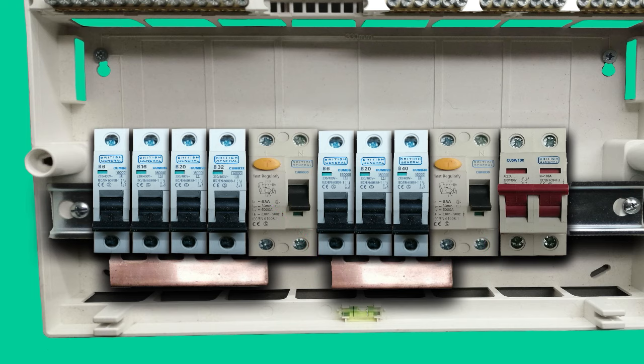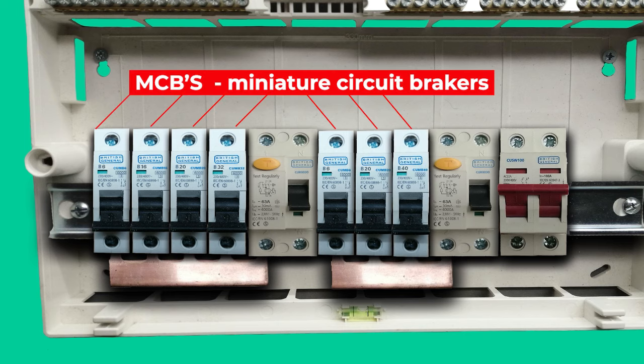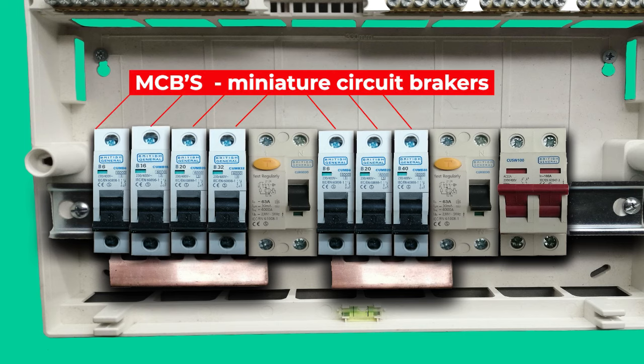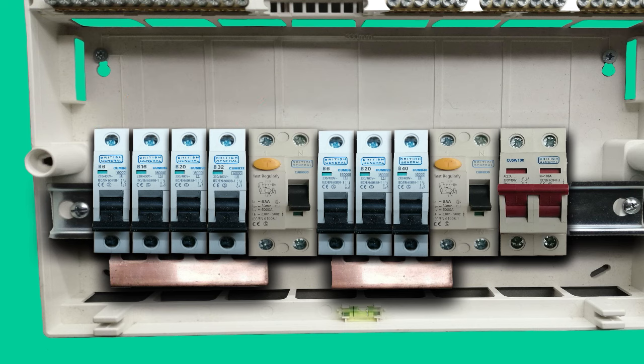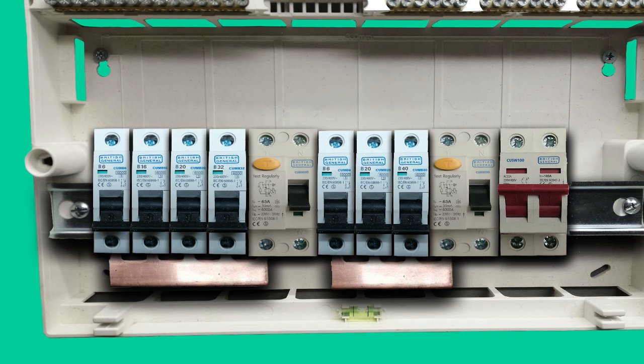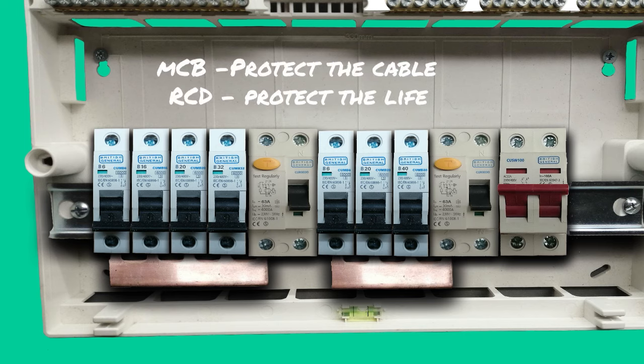And next to the RCDs we've got MCBs or mini circuit breakers. Each one of the MCBs protects one of the electrical circuits from overload as well as short circuit, which can cause damage to the cables and equipment. In other words, if you plug too many appliances to one circuit and they draw too much current, then the circuit will be overloaded, the MCB trips and cuts off the supply in order to protect the circuit. Simply, the MCBs protect the cables and the RCDs protect lives.